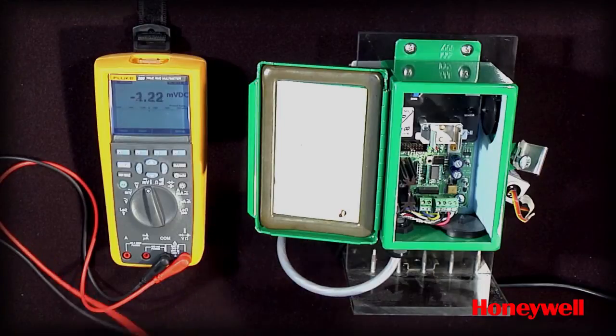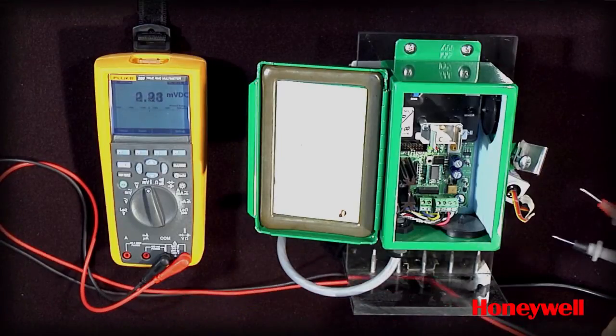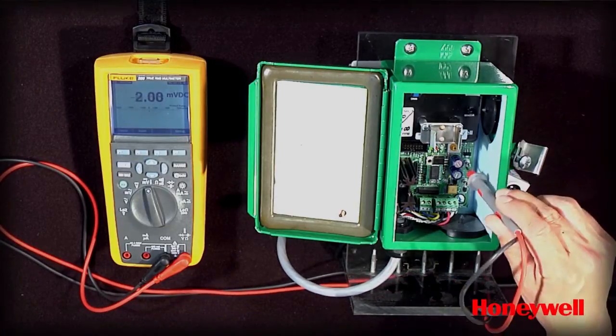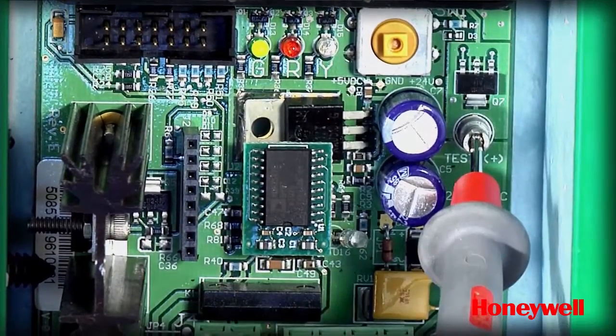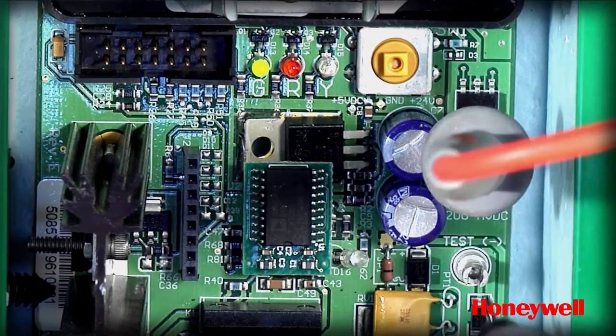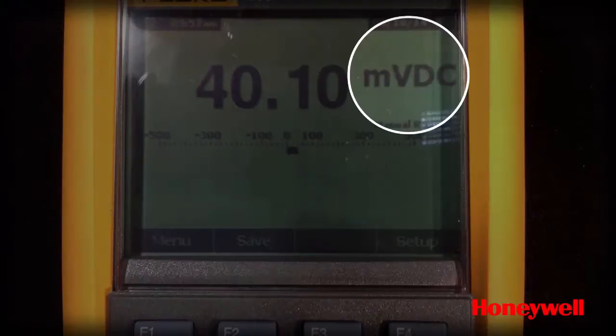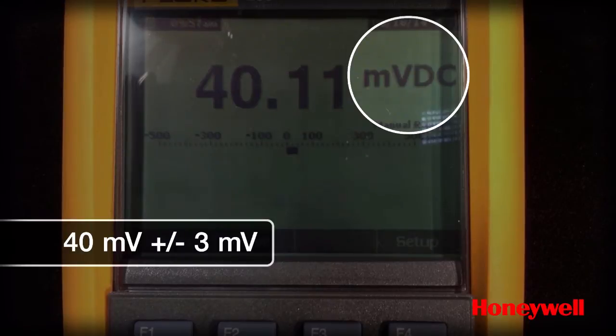Once in factory calibration mode, you will need to attach a multimeter. The red lead goes on the positive test point marked on the board, and the black lead goes on the negative test point, also marked. Make sure you are set to millivolts DC. Your output signal should be about 40 millivolts.